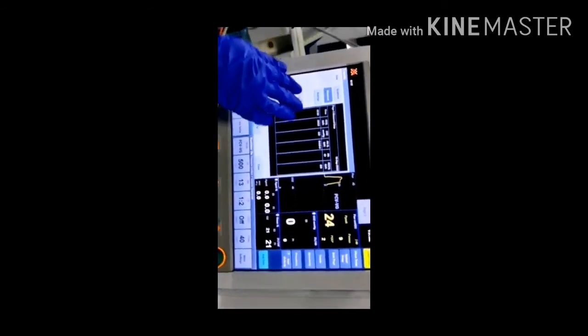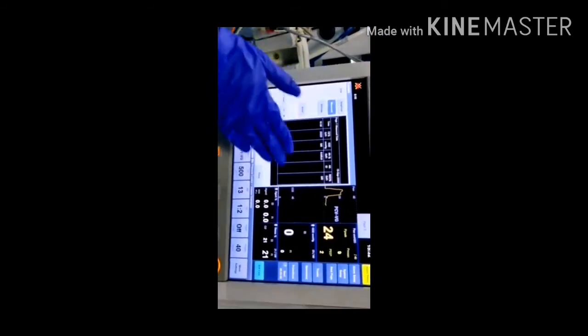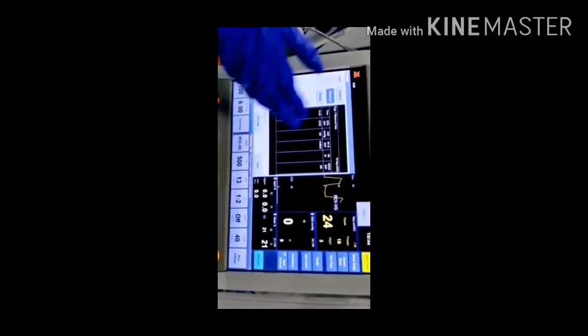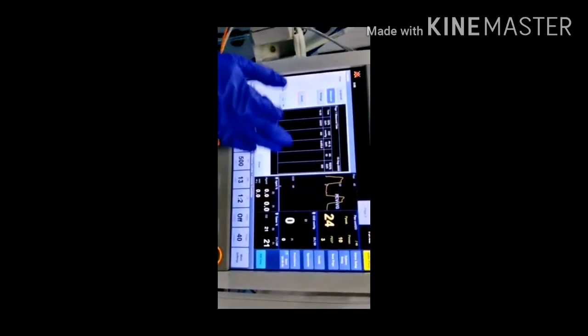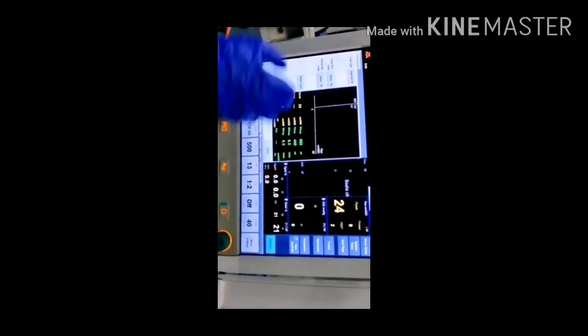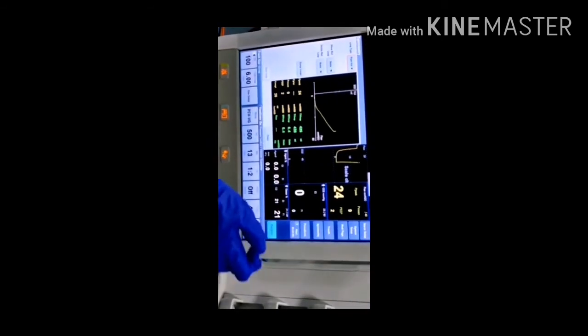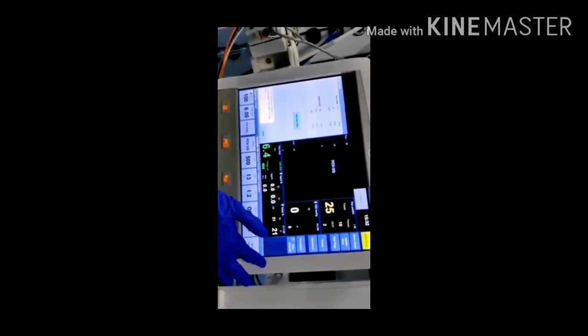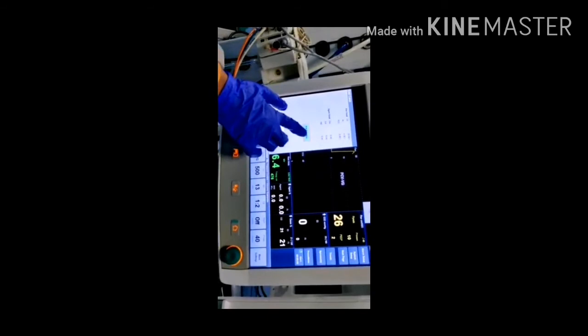For trends, this gives a data of your O2, CO2 and nitrous, air, whatever is supplied, that data is available over here. This is the spirometry as explained. Whichever graph you want, that would be displayed on your screen. And then this is the start time and the end case. So in case you want to stop it, you can just press end case, and you can end the case now.